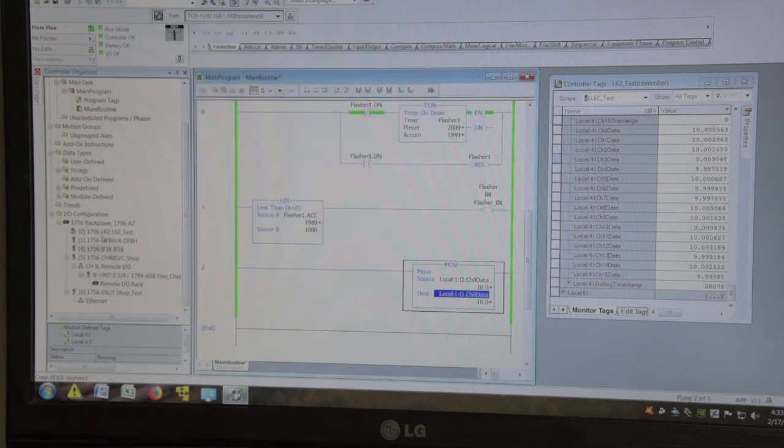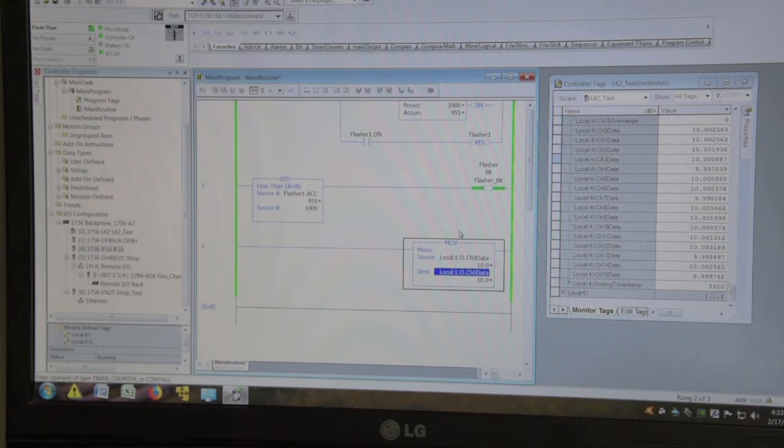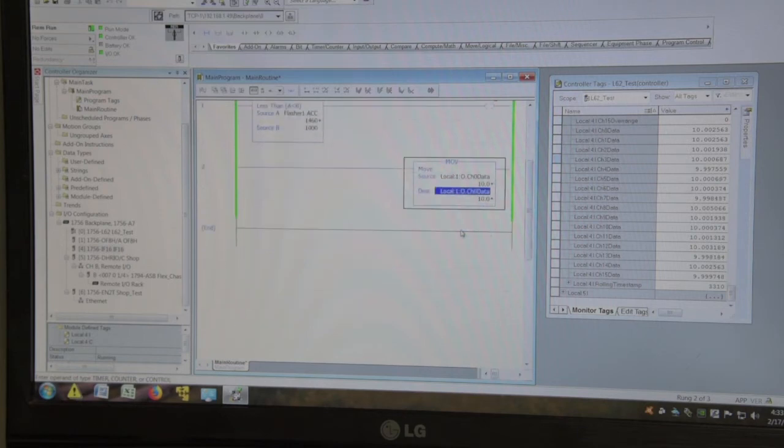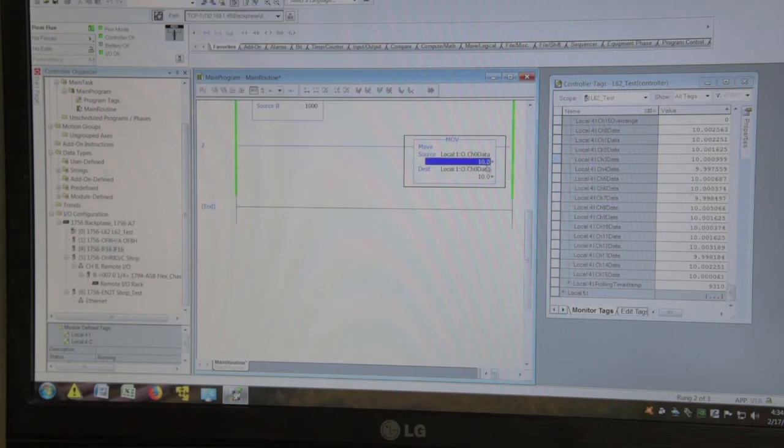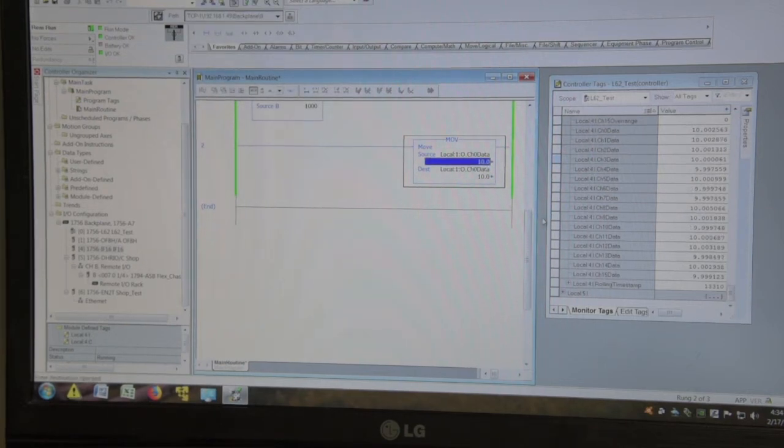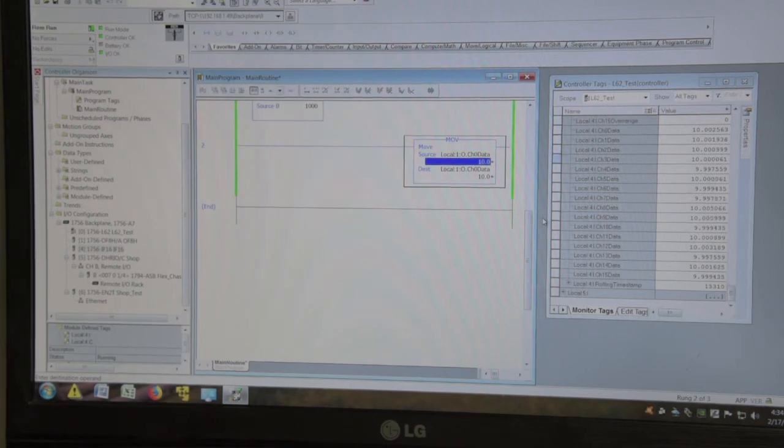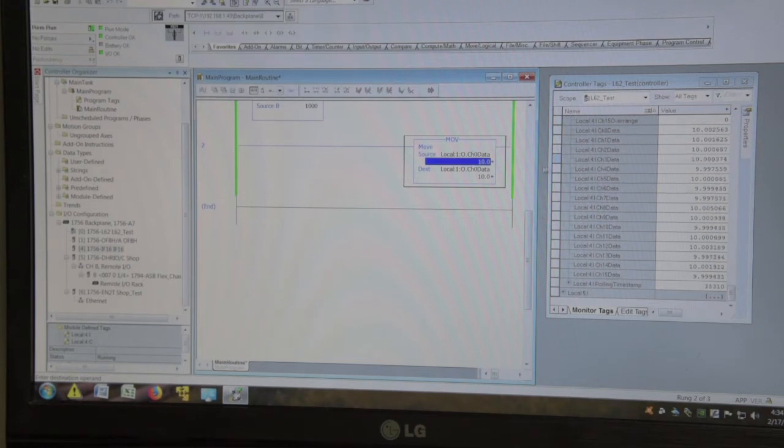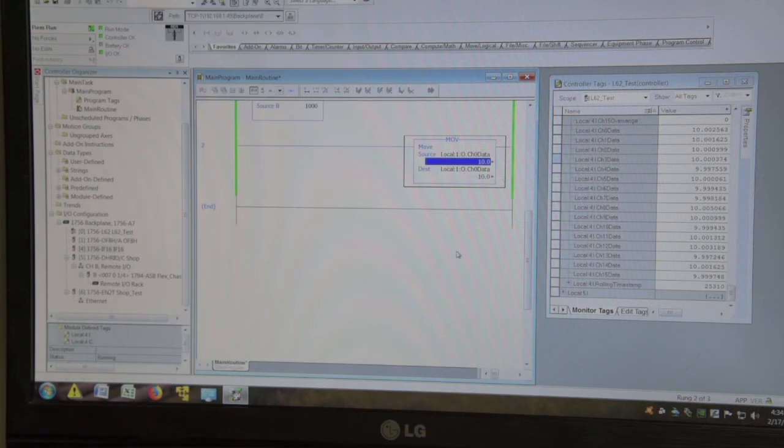The analog output, I've done the same thing. Set it to plus minus 10 volts. So our main rung that we use is our move statement. We're going to move the voltage we want because we're calibrated and everything is in floating data. Currently, we're sitting at 10. And all I'm doing is moving channel zero data into channel zero data.